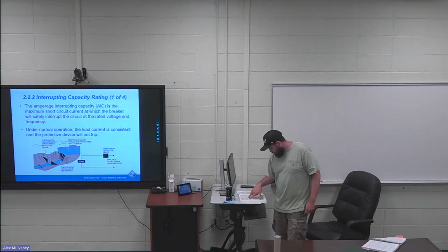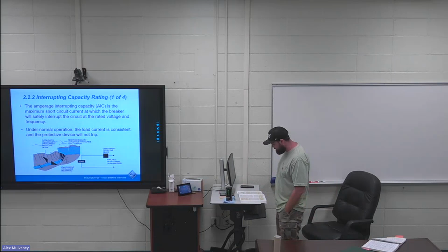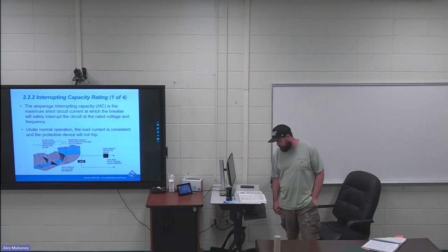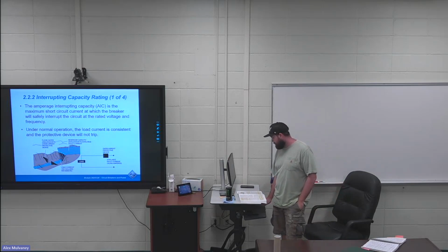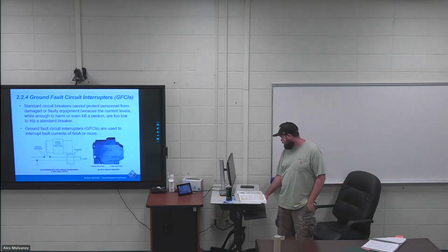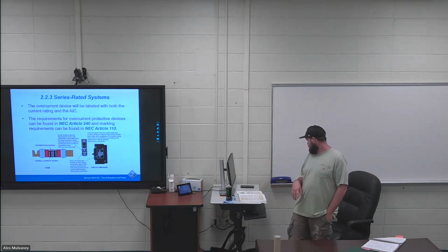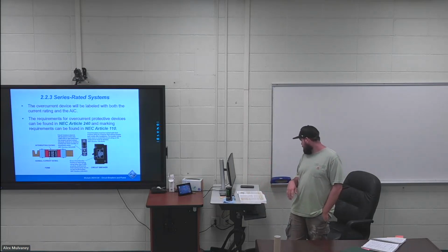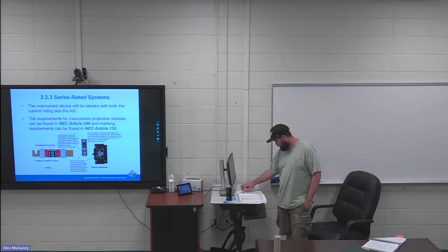Third paragraph on page 10, first sentence is an online test question. At currents below a threshold of about 1,000 amps, the current limiting circuit breaker performs in a manner similar to a conventional thermomagnetic circuit breaker. That's a regular circuit breaker, just like a regular circuit breaker, kind of like you'd see. I guess kind of a circuit breaker you see on the bottom right there, or on the right side of page 11.